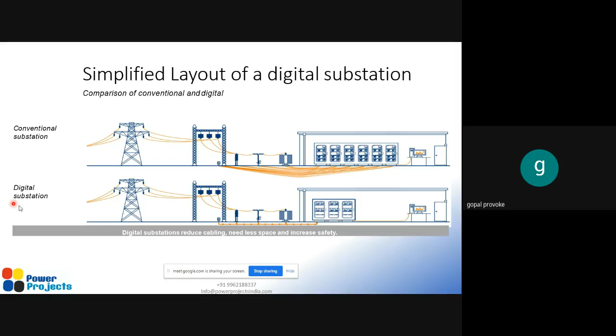This is an overall layout of a digital substation. We have a transformer, non-conventional instrument transformers like optical CT and optical VT, and all these equipments are connected using the IEC 61850 protocol. Transformers, CT, PT, circuit breakers, isolators, everything is connected, and the status and operation of these equipments is transmitted in the form of data.